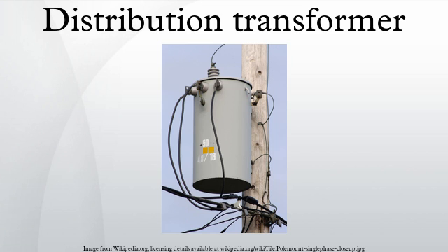As they usually don't operate at full load, they are designed to have maximum efficiency at lower loads. To have better efficiency, voltage regulation in these transformers should be kept to a minimum. Hence they are designed to have small leakage reactance.